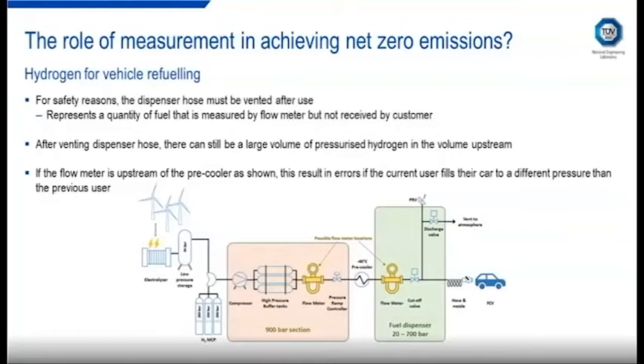There are also dead volumes in the refueling station. These are sections of pipe which connect the outlet of the flow meter to the receiving vehicle. And those sections of pipe will be filled and emptied during the refueling process. Depending on the sequence, the mass in those sections of pipe can change, and that's what's called a dead volume. Again, that has to be accounted for, otherwise it forms a large part of the measurement error.